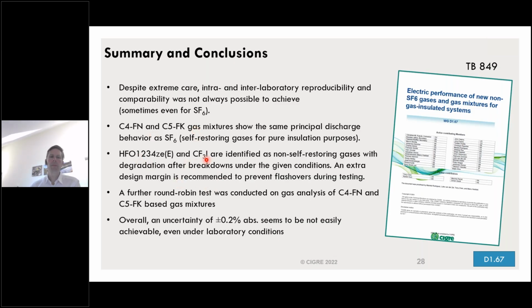HFO and CF3I have both been identified as non-self-restoring gases. Sometimes the degradation is so severe that, for example, in the HFO, carbon fiber bridges were formed, so that the breakdown voltage level was basically 0. CF3I left a very unpleasant stain on the electrodes, which was very difficult to remove. So these are definitely not suitable for high voltage insulation.